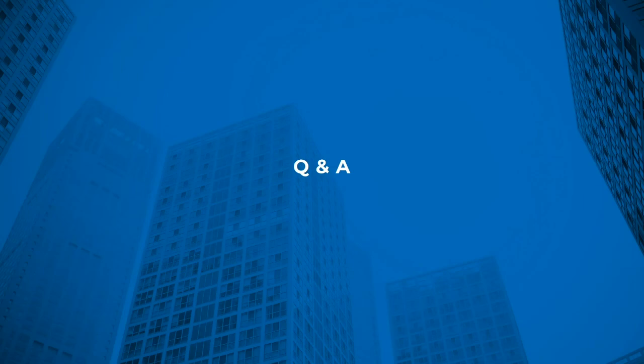The first question is, has anyone looked into hydroxyl or hydrogen peroxide generators? There is a type that can be installed on air handler units and can run continuously while occupants are in the building. I can answer that one. We have looked into generators such as that, and it goes back to you having to make the path of travel for ductwork hundreds and hundreds of feet. I would say on a smaller closed air handler, that could be an option. The downfall is the replacement of having to put peroxide in the unit continuously, day after day, depending on how much you use, as well as it's still not a proven disinfection method by the CDC or ASHRAE or the EPA. But it is something that we have looked into. I wouldn't say that it's off the list as something that we would recommend, but it certainly would take some more research.